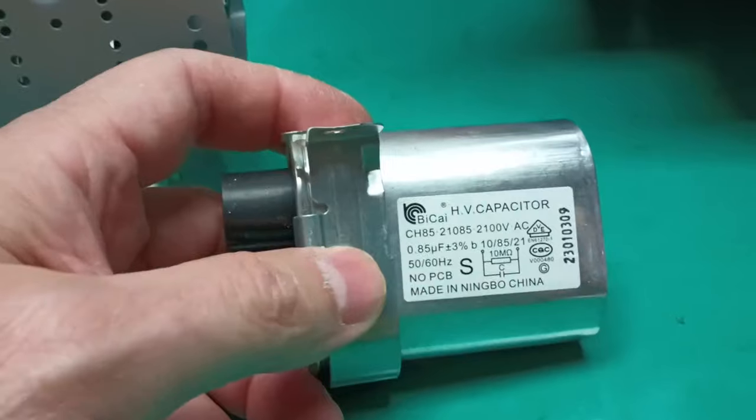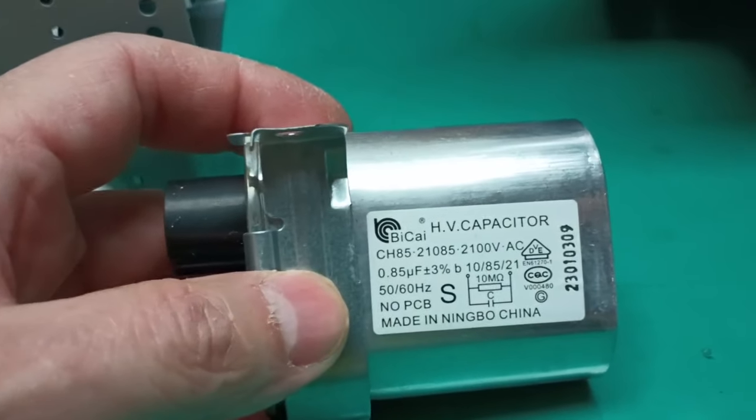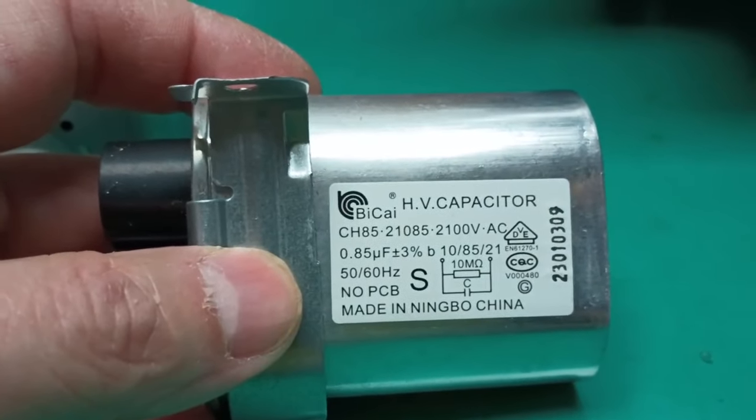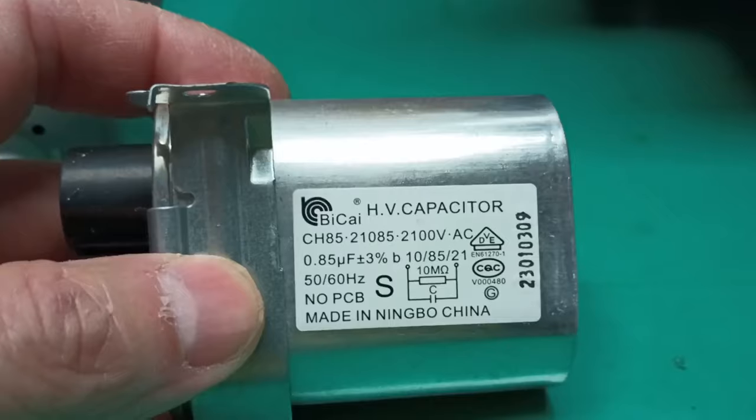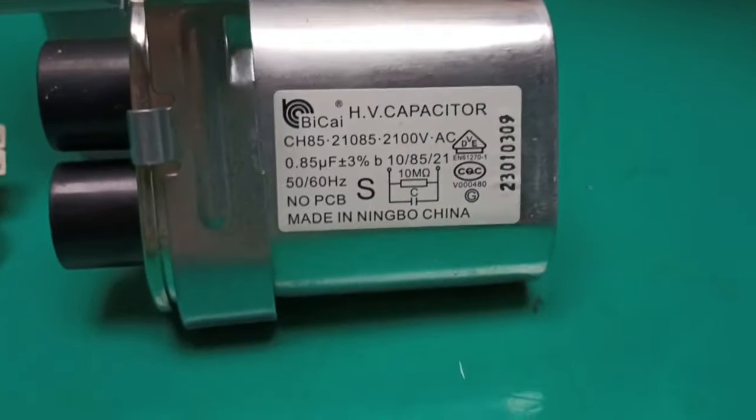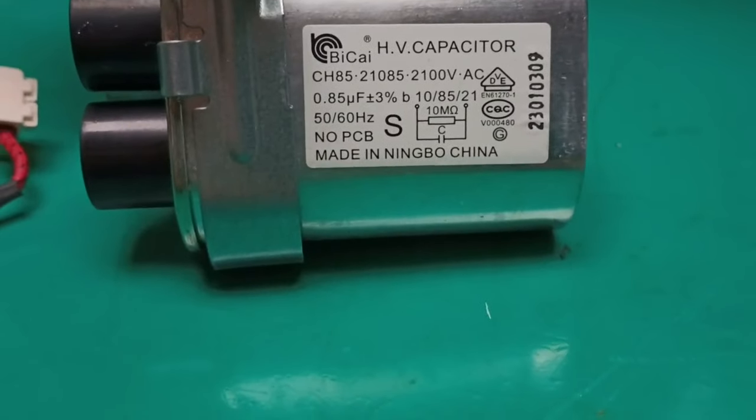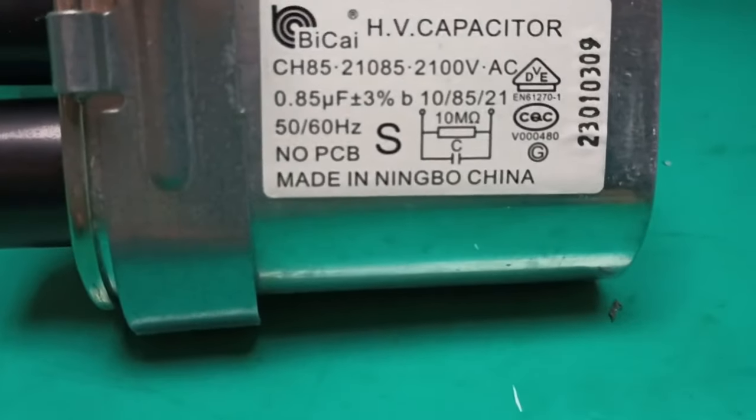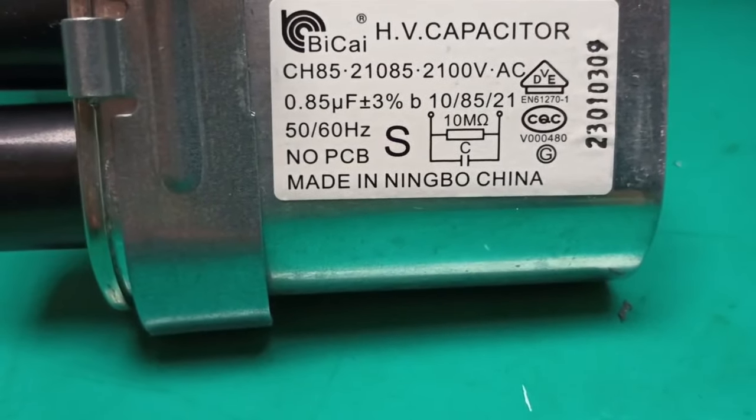And that's all there is for the supposed filter capacitor. And it is and it isn't. Notice it's 0.85 microfarad, 2100 volts AC. Doesn't that remind us of a motor start capacitor? Well, yes, that's how a start cap would be rated.